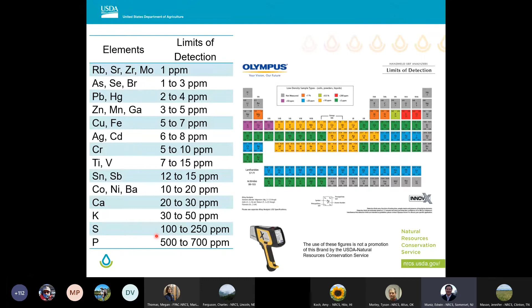For example, here there is mercury. In reality, I don't have too much confidence in this equipment for mercury. Mercury is one of those elements that usually occurs in low concentration, and most of the time it's measured in ppb, which is parts per billion. You can see that the detection limit is 2 to 4 parts per million, so it's not very reliable for mercury. So this is an example. That's something you have to keep in mind when you're using this equipment, and for the reason you're using it. Like any technology, there are limitations.